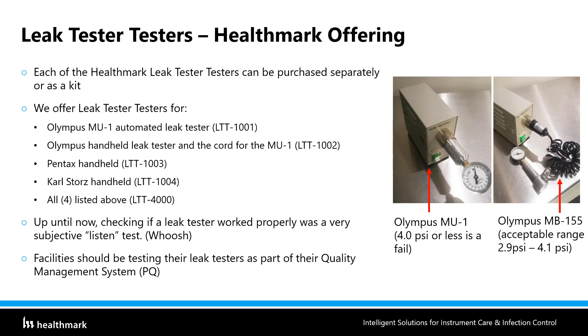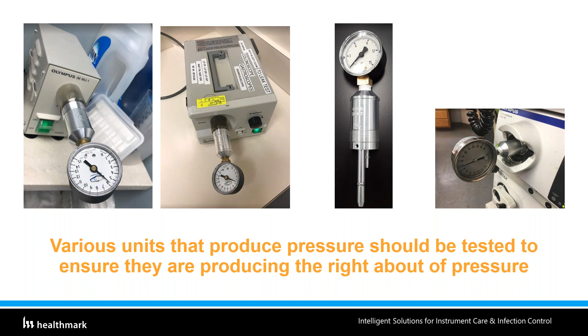So that's the important part for the 50-plus percent: you really need to leak test these, and that's a major issue, because if you don't, cross-contamination could happen and could sicken the patient. And it's not just about having it automated. You go in and see a lot of these manual pumps, and you don't know if they are really providing adequate pressure, or if there's no leak because of the O-ring, or because over time the tubing is starting to dry up.